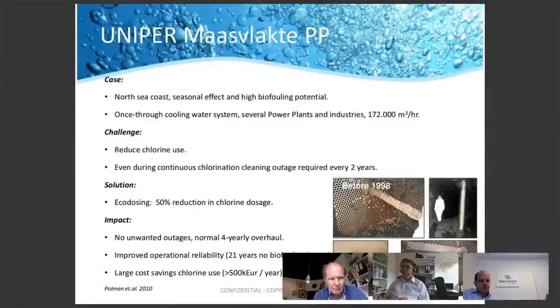This is the Uniper Maasvlakte power plant in Rotterdam, the Netherlands. It's a seawater cooled system. The technology was implemented at Maasvlakte power plant in 1998. Before 1998, they used hypochlorite and a continuous dosing throughout the season to control marine biofouling. We switched the technology to Ecodosing in 1998, and that meant we reduced the amount of chlorine dosed at the seawater intake with more than 50%.